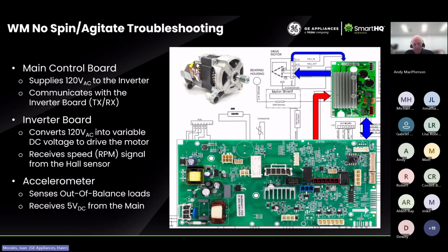We already talked about the resistance at the coils of the motor. That's one of the first things you should make sure it's good. So if you take your multimeter and you measure the resistance and it's 3.5 ohms plus or minus 10%, and again, it depends on the motor, so always look at your schematic, look at the table and schematic diagram. Then that's going to give you whether or not the motor is good.